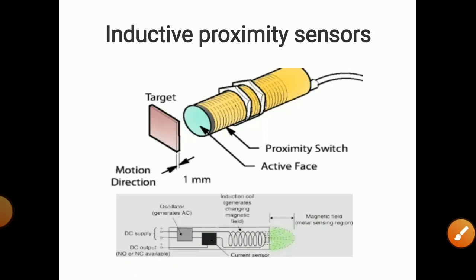When a metallic object comes near the magnetic field, eddy currents are developed on the surface of the object, and some energy is lost from the original magnetic field. Because of this, the sensor detects the change and gives an output — either on or off — indicating whether the object is present or not. This is how the inductive proximity sensor works.